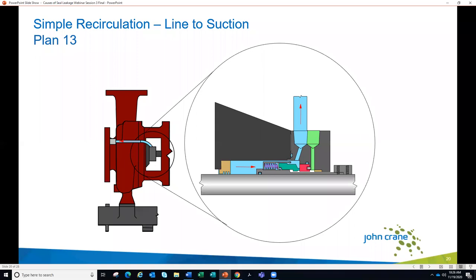Another plan is a line to suction — a Plan 13 — where instead of going to discharge, the line goes to the suction. Since suction is usually at lower pressure than the seal chamber, it sucks fluid out rather than pushing it in. This is popular on vertical pumps because if there is any air in the pump, the highest point is usually the seal chamber, and this line to suction acts as an automatic venting line. A disadvantage is there's usually less pressure differential between chamber and suction compared to discharge, making it harder to achieve a good flow rate. Also, with a line to discharge you can add a cooler or heat exchanger to cool the fluid before it enters the seal chamber, whereas with a line to suction you can't — whatever temperature is in the pump flows directly over the seal.